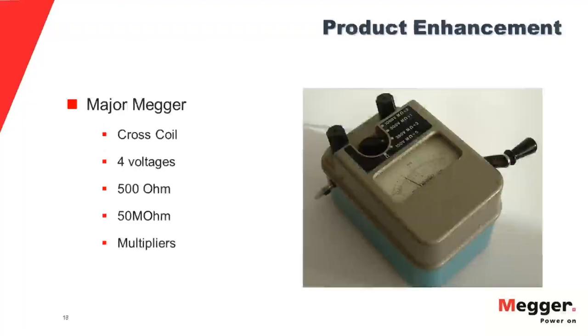And as we moved ahead, the Meg types were replaced eventually by what are called major Meggers, and these are still on the market today, very similar to the one we see here. This is one of the original ones. They're not exactly the same, but they're very similar. You'll note, if you can look closely enough at the scale plate on there, that it only read direct at one voltage. And to use other voltages, we started to add multi-voltage capabilities. But to use them, you had multipliers or dividers that you had to correct the reading to. And as we go along, we'll see how improvements have eliminated over the years some of these early impediments, or whatever you want to call them, to the full implementation and the correct implementation of these units.